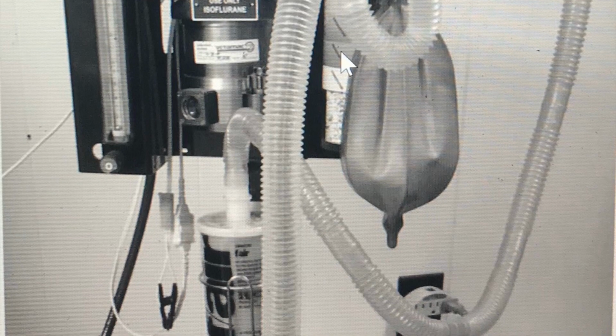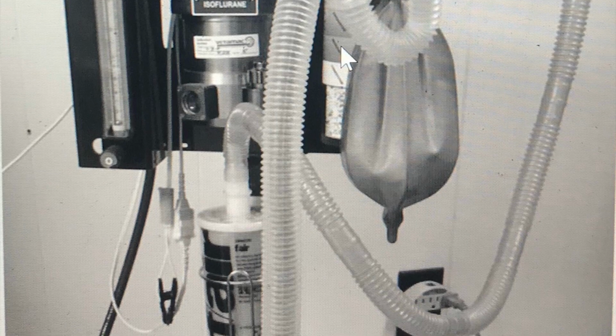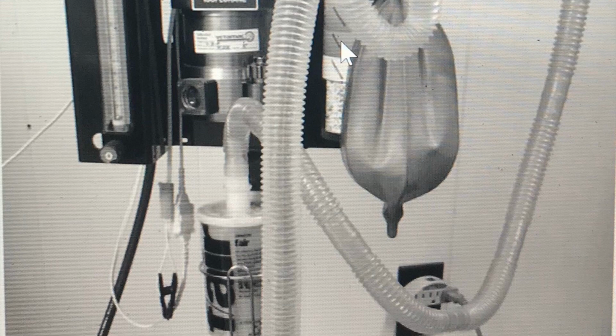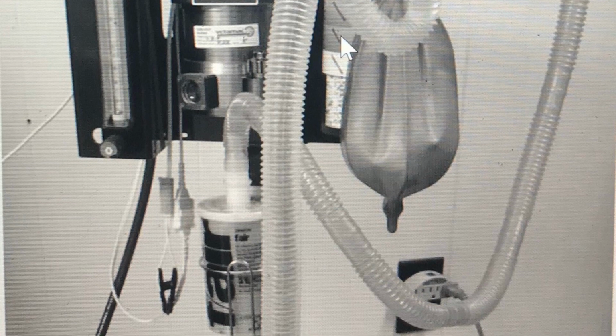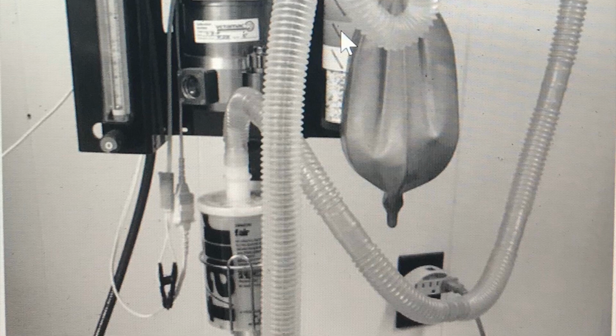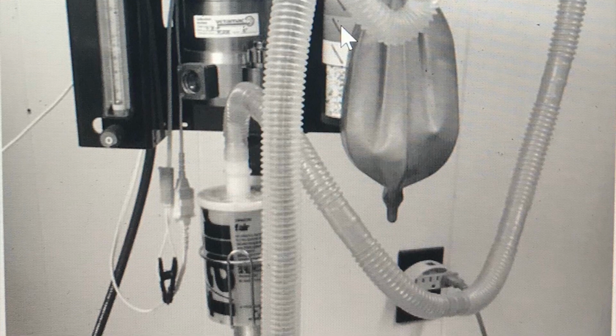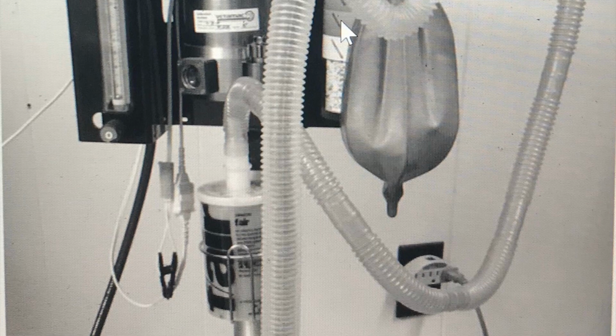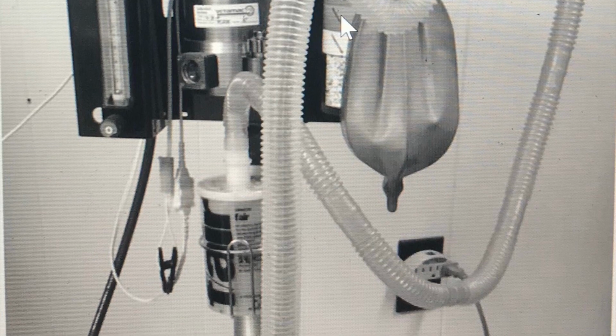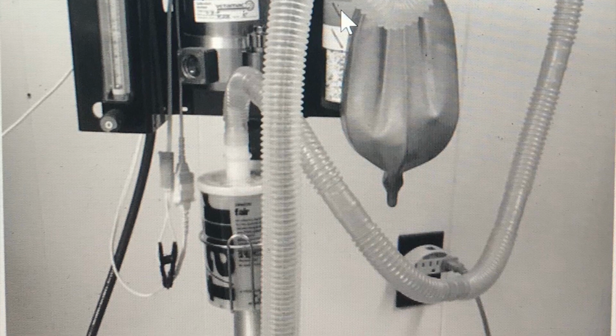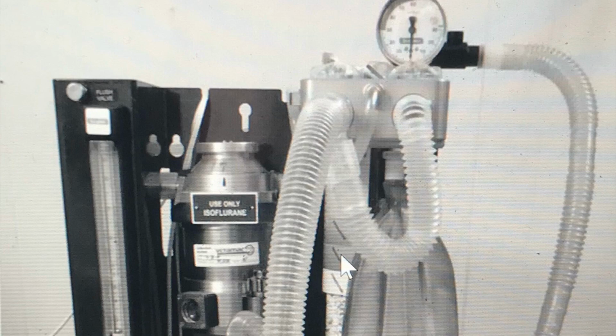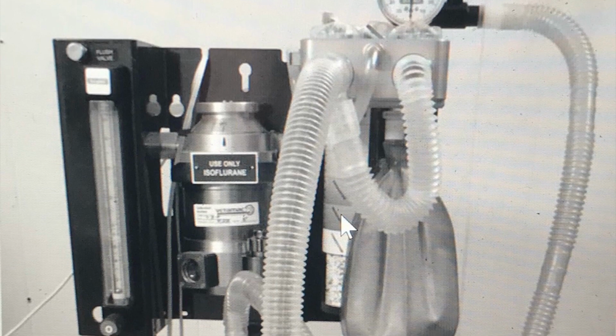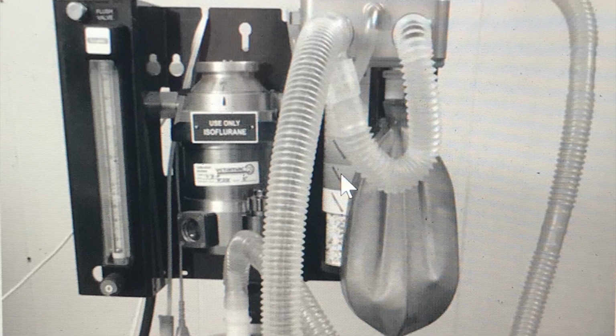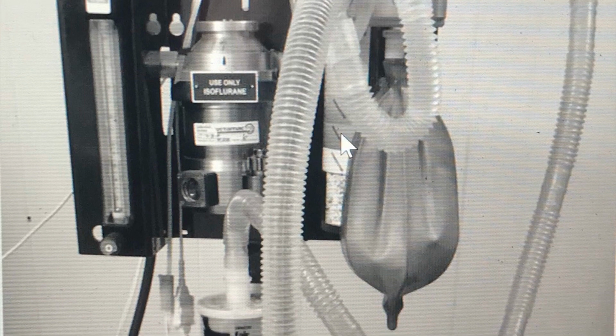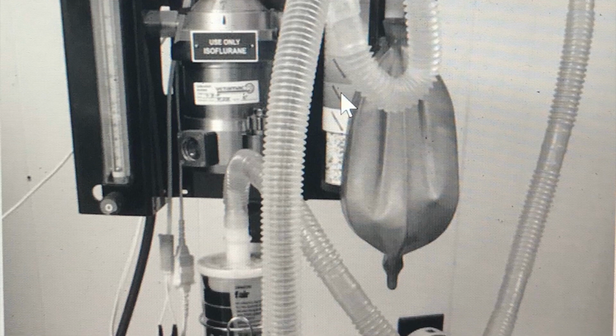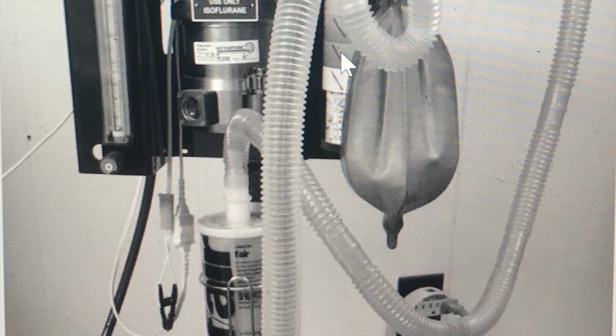After this, you can finally check your pop-off valve and scavenge system, and you'll be done checking your machine. In this case, you will open the pop-off valve, occlude your patient's tube, turn on the oxygen to 4 liters per minute, and then you will check the manometer and make sure that it does not read more than 2 centimeters of H2O at this flow rate. Because if it increases, then there's something keeping the scavenging system from emptying properly, and you need to fix this prior to use. Also, be sure to check that your scavenging system is not expired. If it has gained more than 50 grams, you must change it. And for this surgery, I will be attaching a Y-piece tubing for my patient and a 1-liter bag based on her weight.